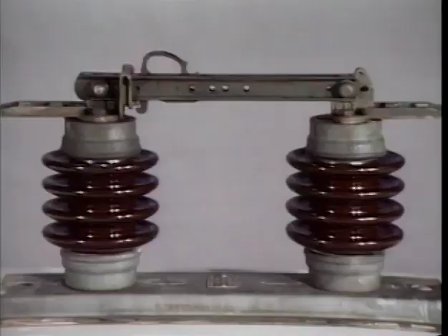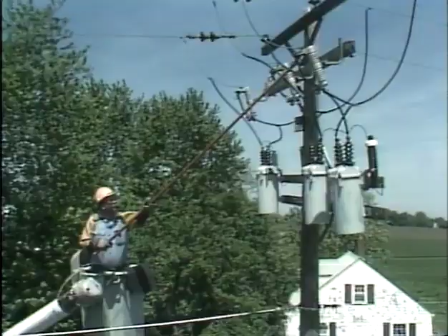This is one kind of no-load disconnect switch. It's called a no-load switch because the circuit must be de-energized before this switch is opened. Its parts include a disconnect assembly, a switching arm, and switching contacts here and here on the switching arm. Note that the switching arm is made of one solid piece of metal. In this case, it's a knife blade. When a circuit has been de-energized, the circuit can be isolated by separating the switch contacts. This creates a visible break in the circuit. There is no arc to extinguish because the circuit was previously de-energized.